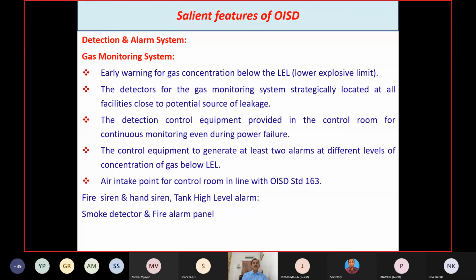The control equipment should generate at least 2 alarms at different levels of gas concentration below LEL. One will be at 20% of LEL and the next at 60% of LEL. And the air intake point for the control room is in line with OISD standard 163.